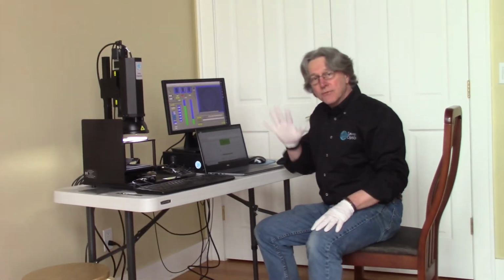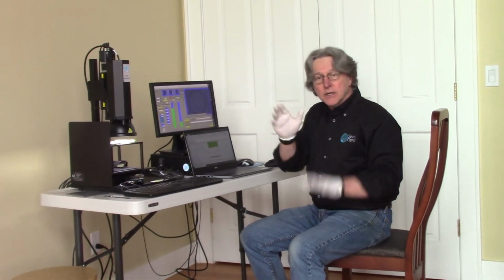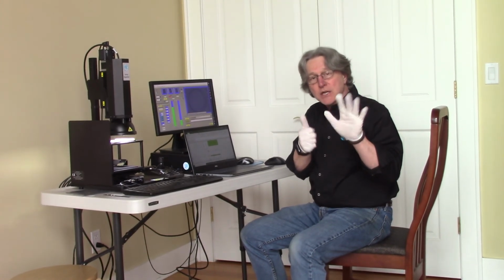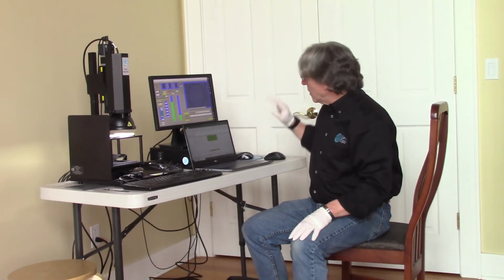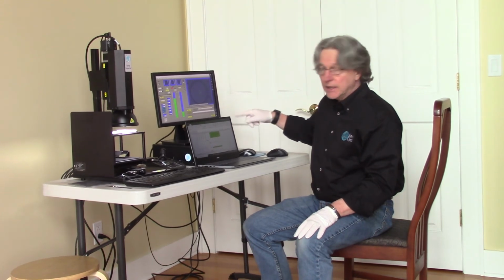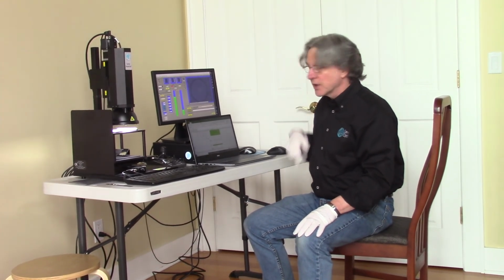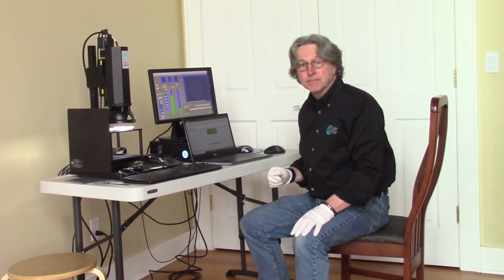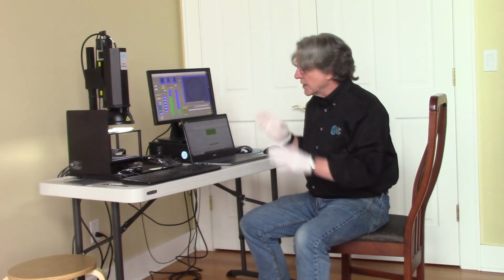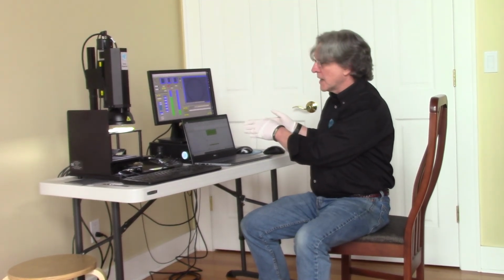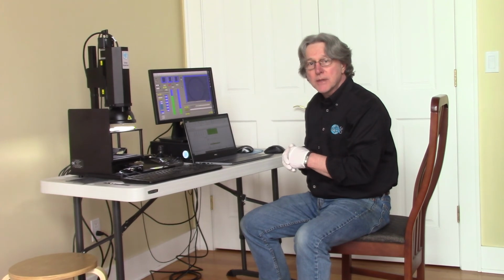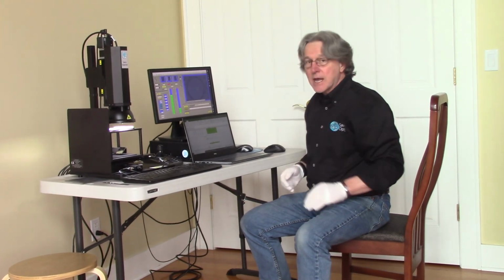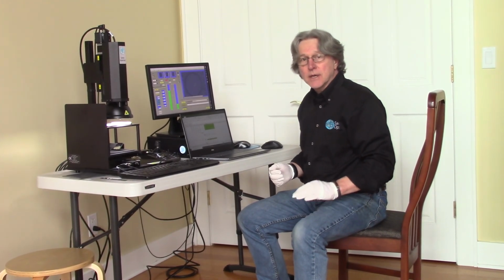So in all, you have 5 dig measurements, and then you have 6 measurements per scratch for 5 scratches. All that data goes into the spreadsheet, and you check to make sure that all of your values are within the allowed limits. Okay, that's it. So then if everything's consistent with the requirement, then your system is calibrated, the calibration is still valid.